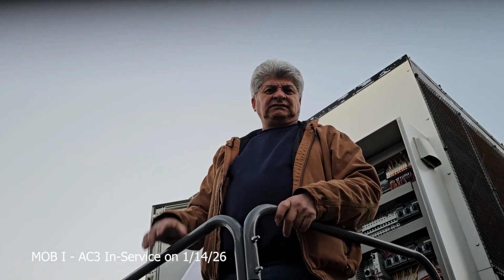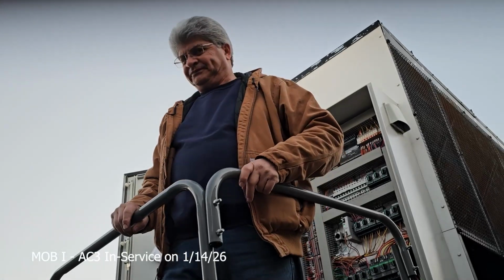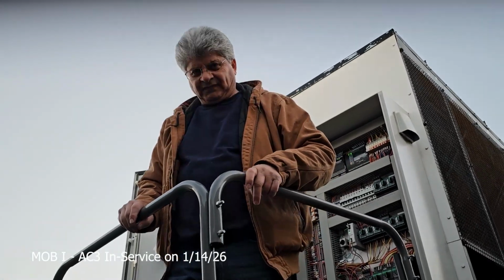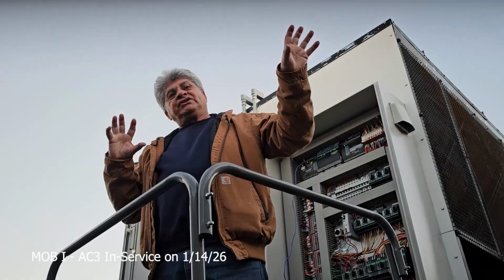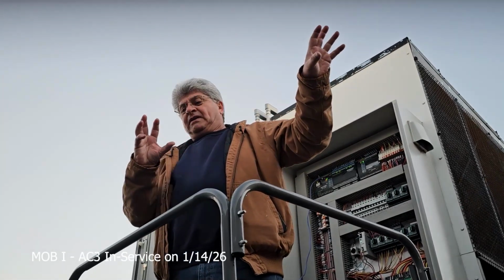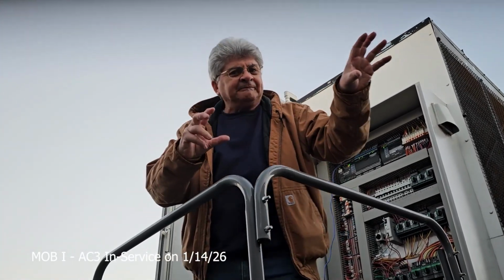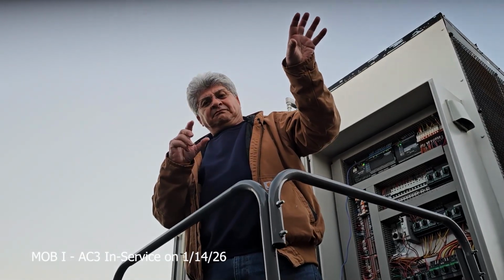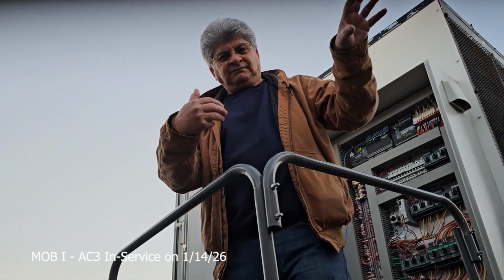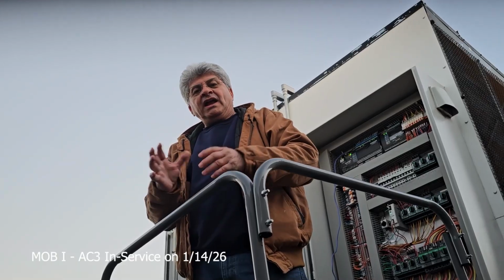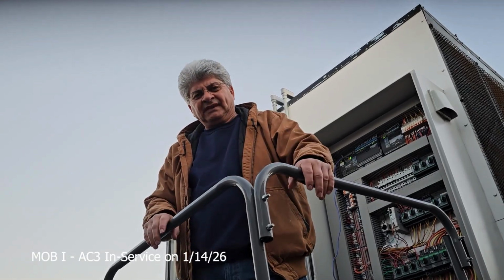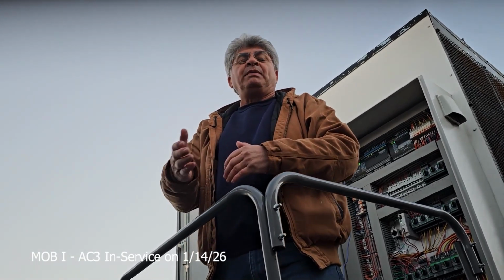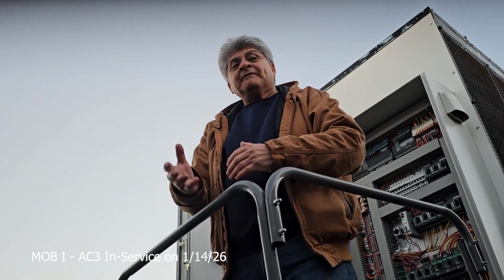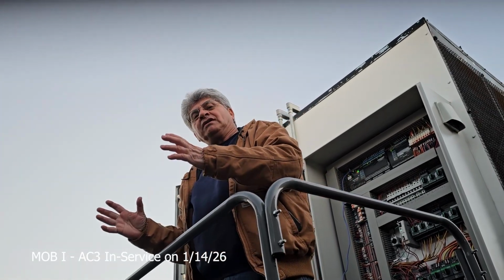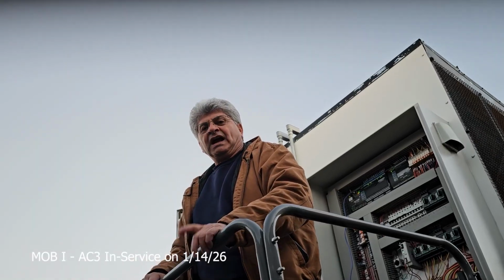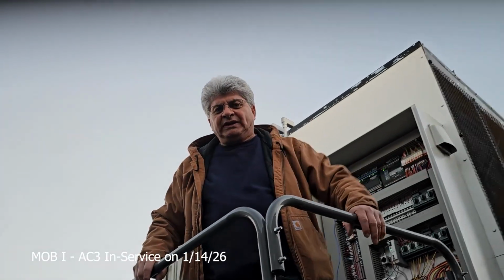Are they the same size? No, the supply and return are different sizes. And they follow each other. So if the motor senses that it's pulling more than it should, it'll protect itself from burning out. It may go into an alarm and it'll be an automatic reset. But if it pulls high amps for too long, it'll be a manual reset. I'll show you when we get back there. I'll show you what that looks like.